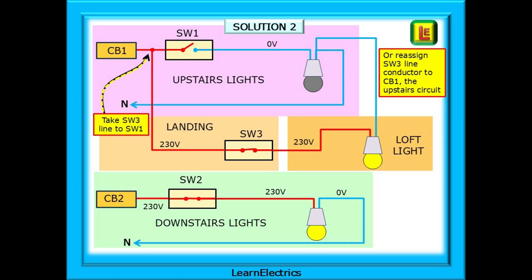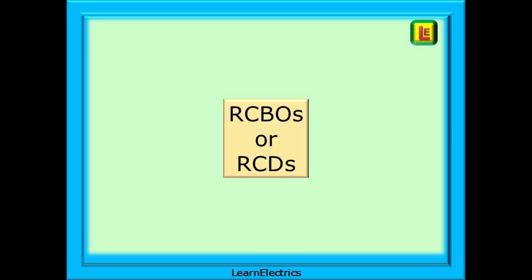Alternatively, reassign the 230 volt line conductor that goes to SW3 back to the circuit breaker number 1, the upstairs circuit, so that the line and neutral are both controlled by the same breaker. Now, isolating CB1 will isolate the upstairs lights and the loft light.